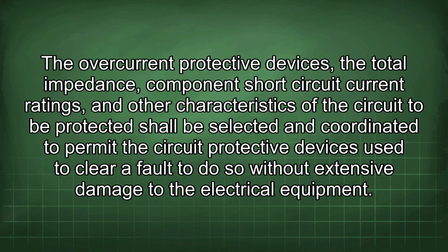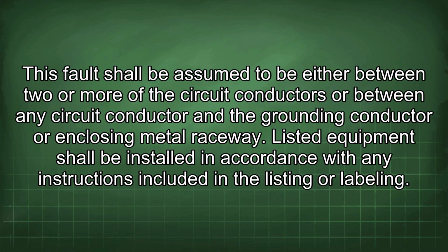The overcurrent protective devices, the total impedance, component short circuit current ratings, and other characteristics of the circuit to be protected shall be selected and coordinated to permit the circuit protective devices used to clear a fault to do so without extensive damage to the electrical equipment. This fault shall be assumed to be either between two or more of the circuit conductors or between any circuit conductor and the grounding conductor or enclosing metal raceway.